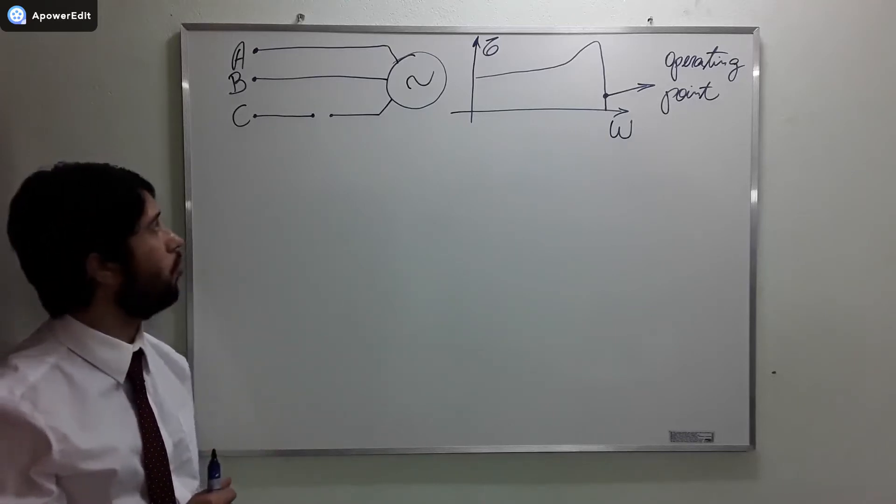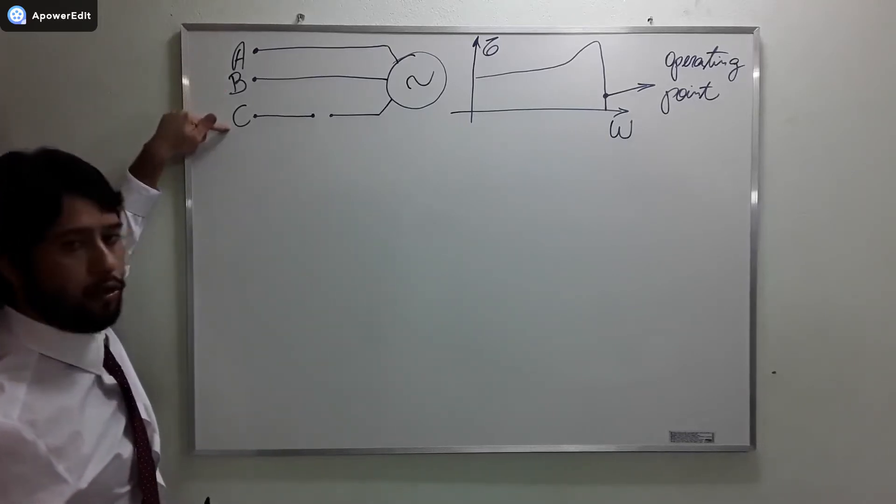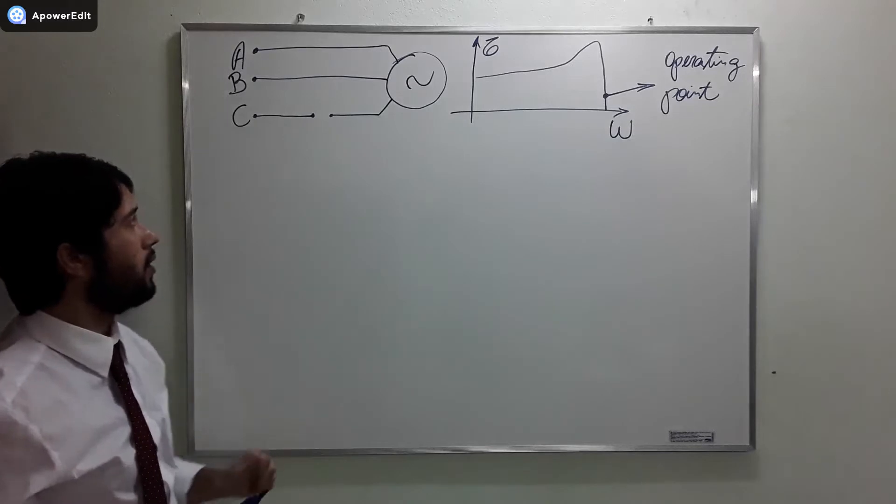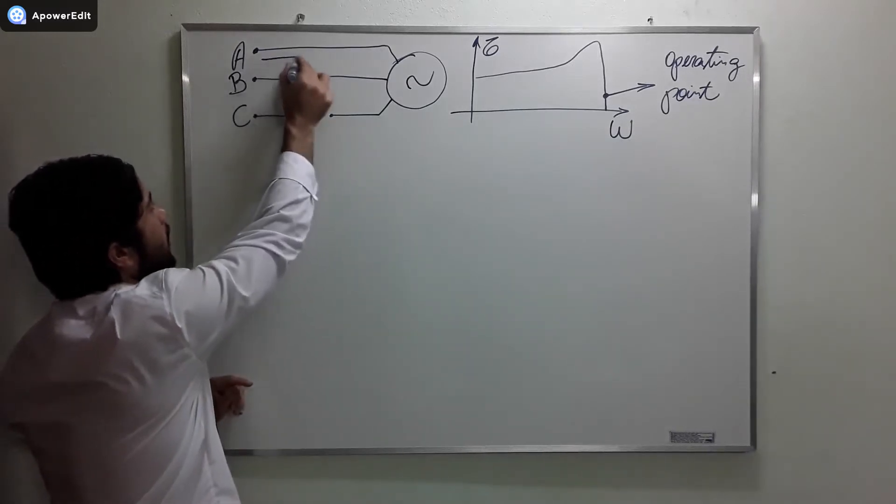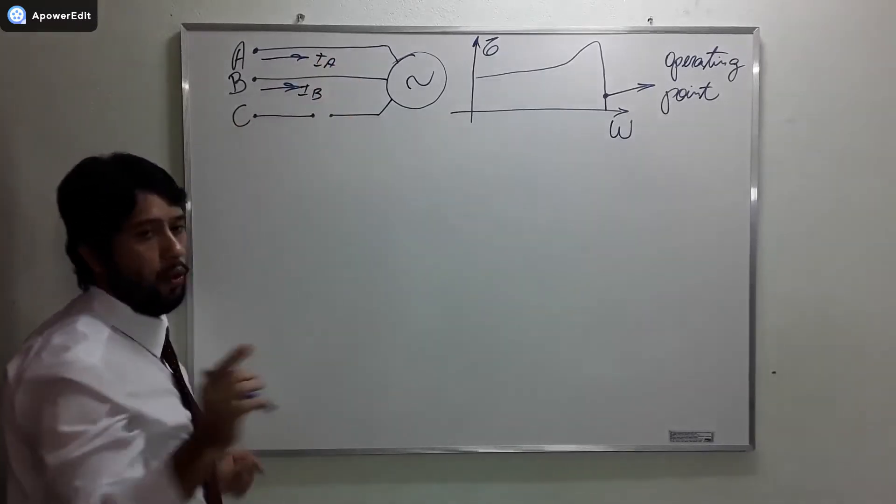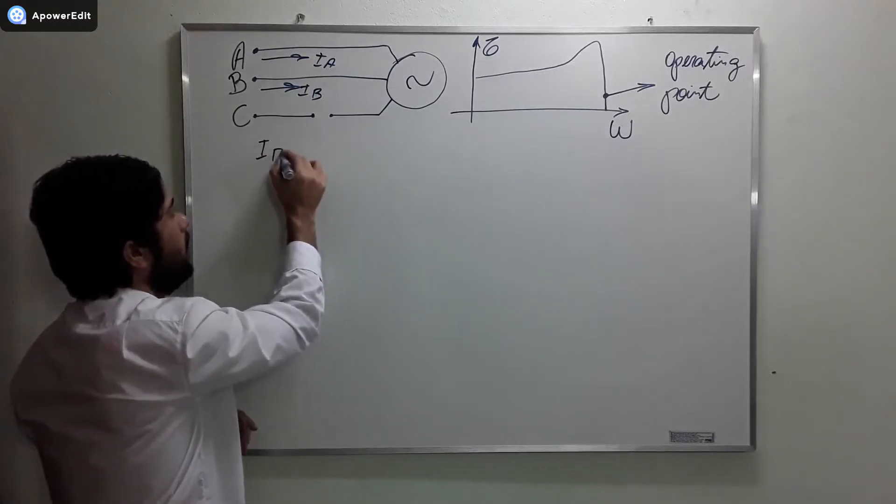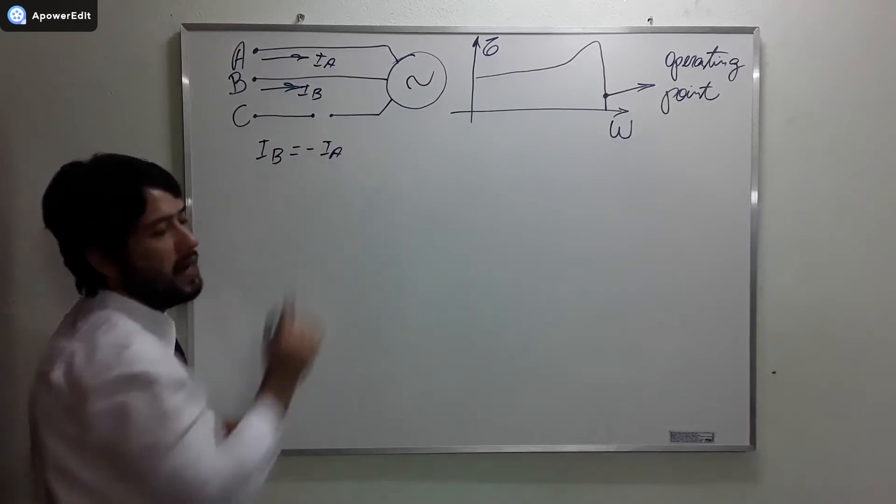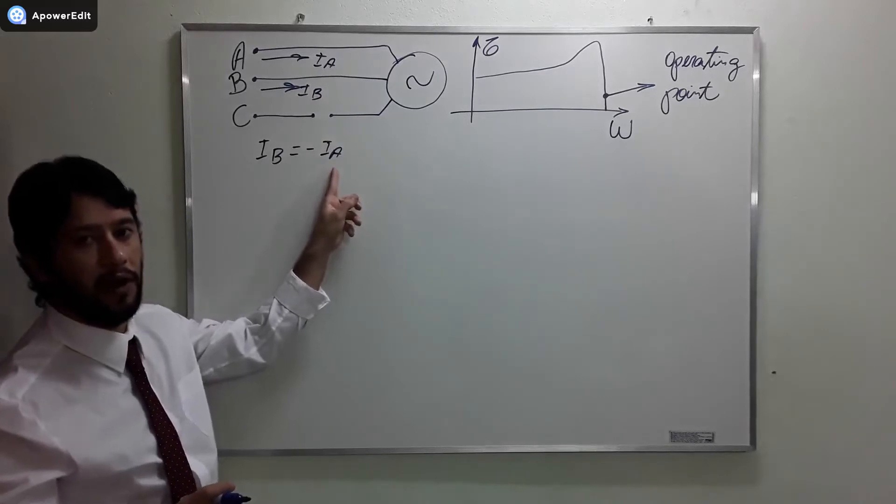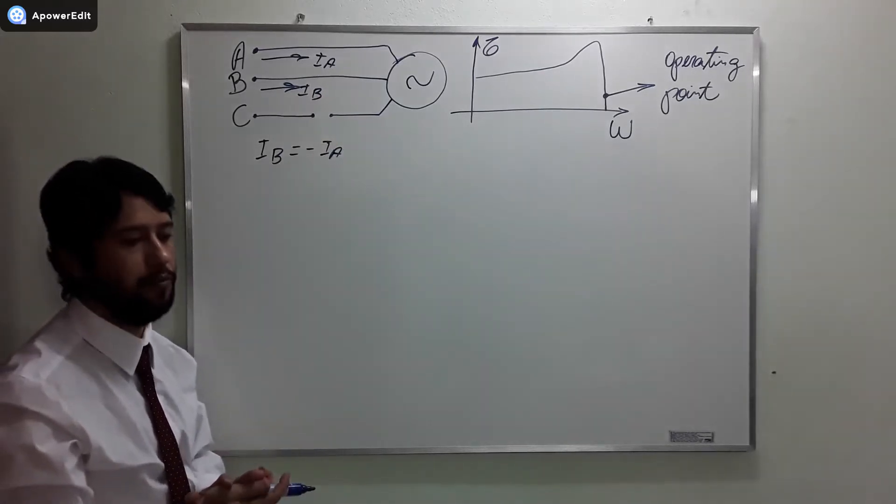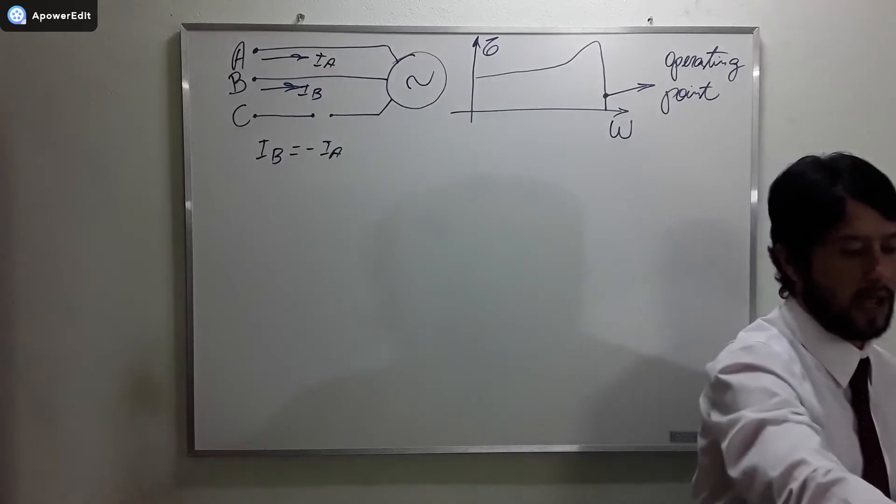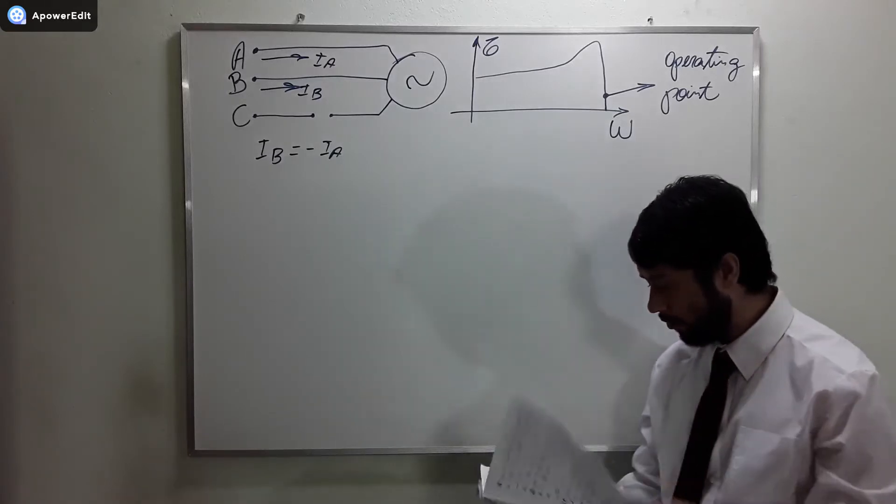Why do I say single-phase motor? Because when I have three phases, the motor behaves as a three-phase motor. But if I lose phase C and I have only current IA and IB, we can prove that IB is going to be the return of IA and the motor is behaving as a single-phase motor. This helps us understand what's going to happen after we lose one phase.